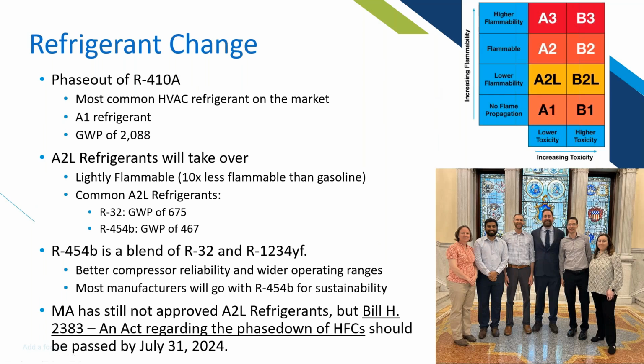What does that mean? It means a big phase out of R410A refrigerant, the most common HVAC refrigerant on the market. It's an A1 refrigerant, which has a GWP of 2088. That means the A2L refrigerants will take over. And what does A2L really mean? It's just a classification of its flammability and toxicity. A lot of engineers are starting to become a little bit concerned about it being, quote unquote, lightly flammable. As soon as you say the word flammable in design, people get a little bit squirmish, and Massachusetts is as well.